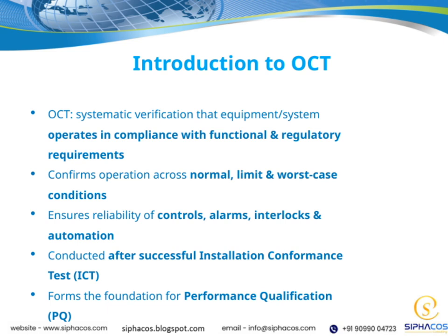This is crucial because it ensures the reliability of controls, alarms, interlocks, and automation features, everything that keeps the system safe and effective. It's important to note that OCT is conducted after a successful Installation Conformance Test, or ICT. Think of it as building on that initial verification, moving into a more detailed validation phase.